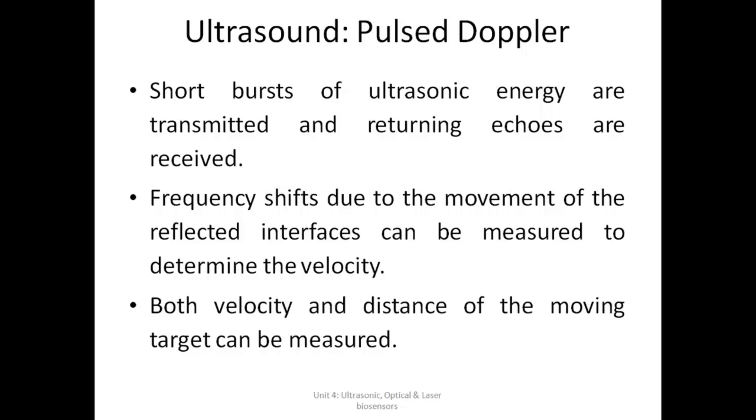When the source is static, you send some ultrasound wave, it strikes the surface, some gets refracted, some gets reflected. That reflected energy is recorded and then calculated in terms of some image. So you get that image of the source. When you apply Doppler effect, then along with the image, you are also calculating the velocity with which the target surface is moving. Okay, so short bursts of ultrasonic energy are transmitted and the returning echoes are received.